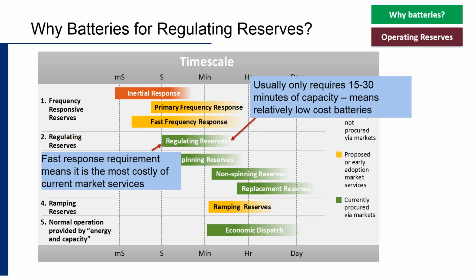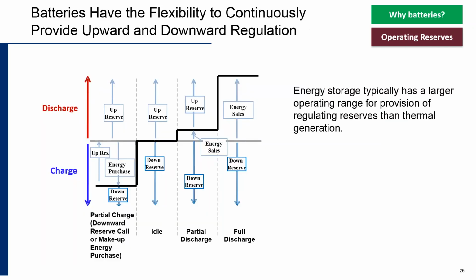Regulating reserves are typically only needed for 15 to 30 minutes, which means you don't need a 4-hour battery—you can build a 30-minute battery, which is relatively low cost compared to longer duration applications. That's why early storage applications in the United States focused on regulating reserves. As I showed, batteries can operate over a large range and do some unique things—for instance, they can provide full-up reserves over twice the capacity of the battery when charging, or provide a lot of downward reserves when discharging. So you need to consider the full flexibility range of batteries when comparing their economics to other alternatives.